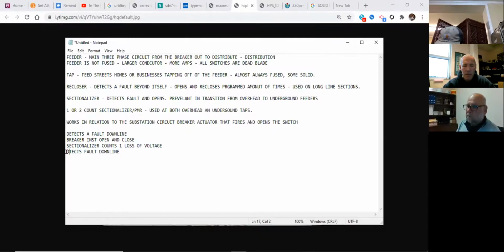I always put detects. Fault downline. What does the sectionalizer do now? I mean, what does the breaker do now? Breaker does timed open. What is the sectionalizer now seeing? The sectionalizer counts 2, 2 loss of voltage. Remember, our breaker has opened up, does a timed open, and the sectionalizer has counted the second loss of voltage.